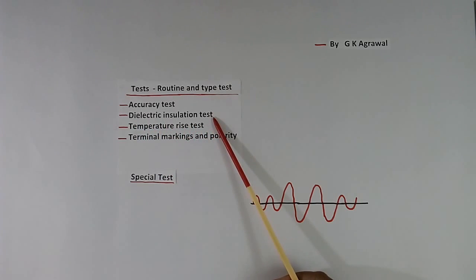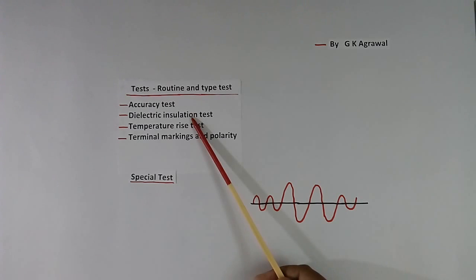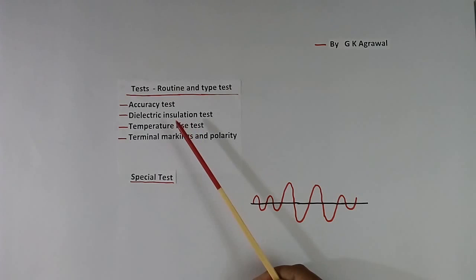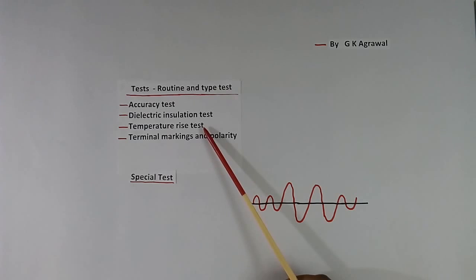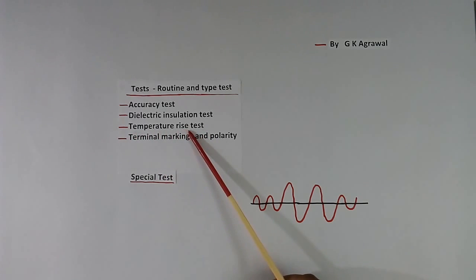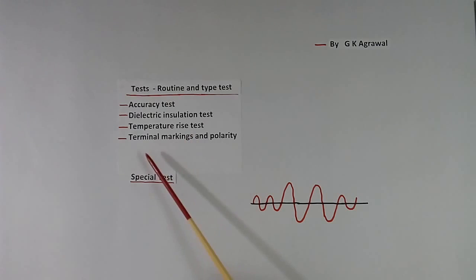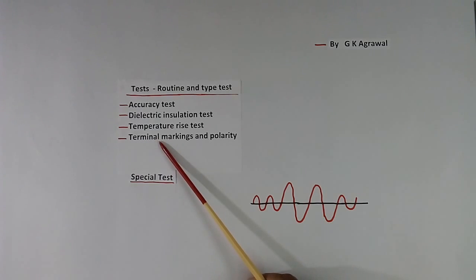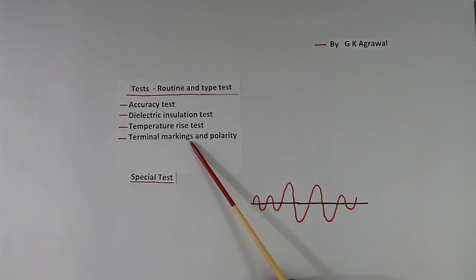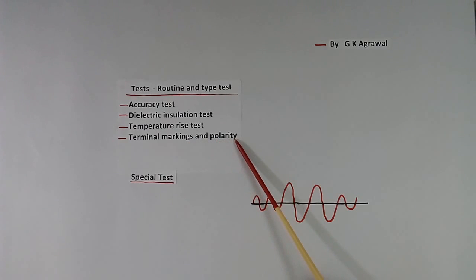Then the dielectric insulation test — we apply high voltage across primary and secondary, or primary and ground, and see whether the insulation can withstand the high voltage. Then the temperature rise test — suppose the transformer is rated 10 VA and the ambient temperature is 70°C. We connect the full load of 10 VA, place the transformer in a chamber at 70°C, keep it on for many hours, and check what is the temperature rise of the transformer. Then terminal marking and polarity — we check whether the terminal type is given properly, such as nut-bolt, soldering, or wire, and whether markings P1, P2, S1, S2 are correct, and polarity is marked properly.